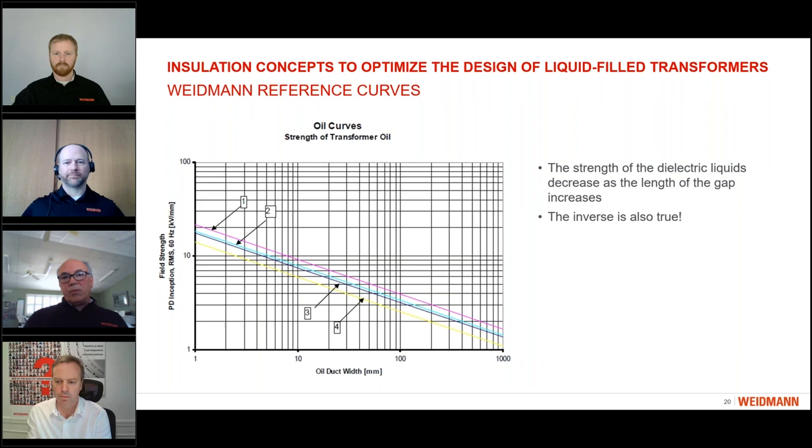So what you measure in a test according to a standard isn't exactly what you would apply when you're designing the transformer. But to finally come back to the original question, you should not use strength in air for designing a power transformer. And I know for the Weidmann materials, we have tests in oil and oil-based criteria.